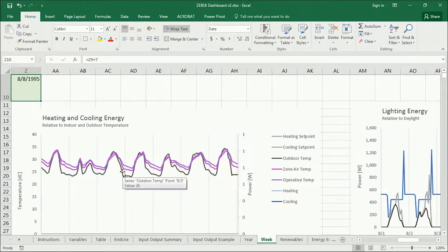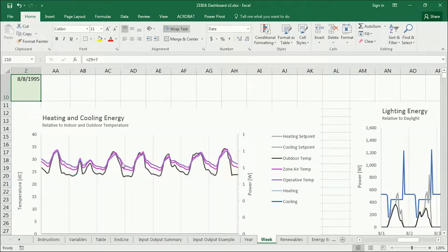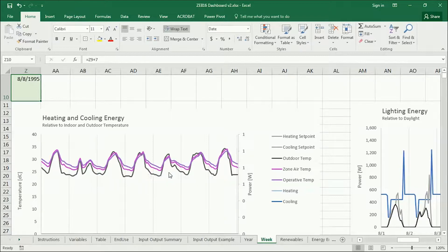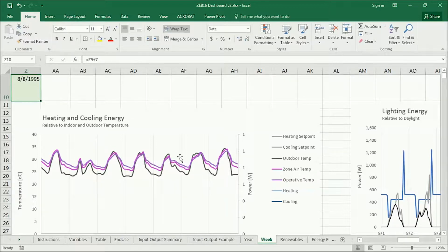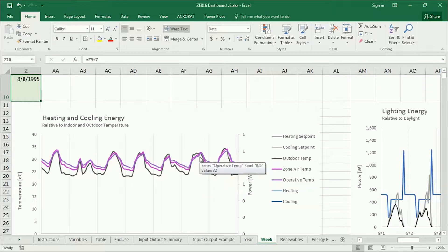You should also know that the thermostat is just looking at the air temperature, so heating and cooling would theoretically turn on whenever the air temperature gets to set point. Right now we've got no heating or cooling system, so there's no heating or cooling turning on — it's just the free running building. You can see that there are in fact some times of day, almost every day, when the outdoor temperature is above the indoor temperature, and so theoretically ventilation shouldn't be turning on.